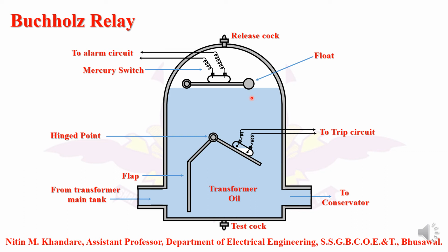If a fast acting fault takes place inside the transformer, then the transformer oil starts to boil, due to which the volume of the transformer oil increases, and that's why the transformer oil rushes towards the conservator tank rapidly. At that time, it rushes towards the conservator tank, but the flap is inside it, and that flap will be pushed. Due to that, the mercury switch contacts get closed, and that closing of the mercury switch contacts gives the signal to the trip circuit, and the circuit breaker can be tripped. In this manner, the Buchholz relay protects the transformer from the incipient, that is the slowly acting faults, as well as the rapid acting faults.